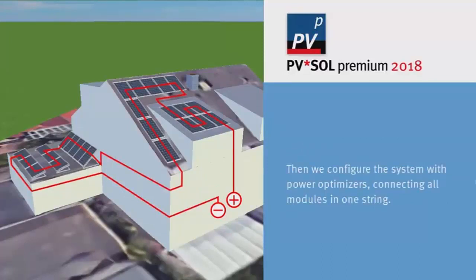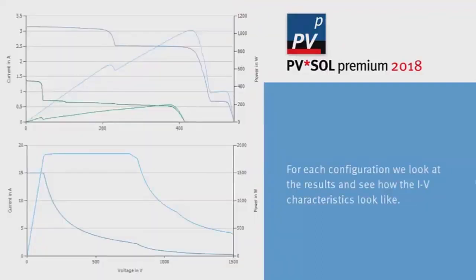on each module, and we'll then examine the differences between the voltage, current and power voltage characteristics between those two choices. Indeed, if we look on the screen at the top chart, the one with all the lines on, you'll see this is the characteristics for the string inverter with two maximum power point trackers. You've got both the power voltage and current voltage curves there, and as you might expect, the situation is quite complex given the number of different angles and directions the modules are facing.